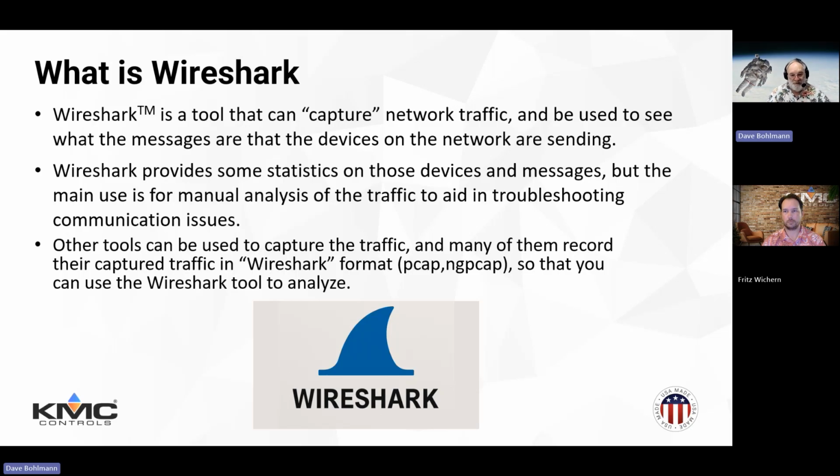The tool in itself provides some statistics on the devices and the messages that are going back and forth. But the main reason we use it is if you have communication problems. Most of the time, all I do is double check my configurations with my BACnet networks, and then I do a Wireshark capture. I capture the traffic and analyze it to see really what's going on without trying to guess, and that really helps to troubleshoot the cause of your problems.